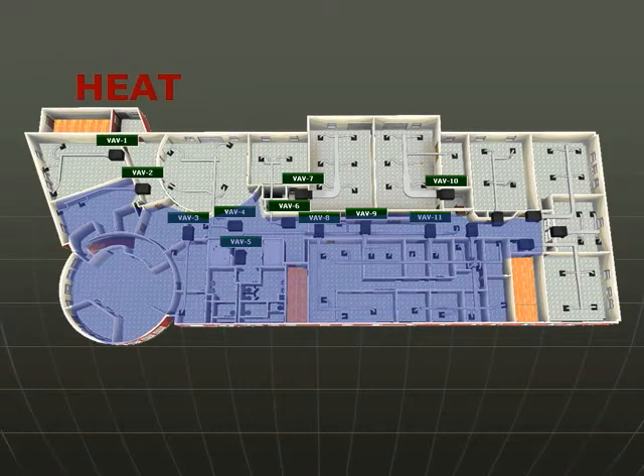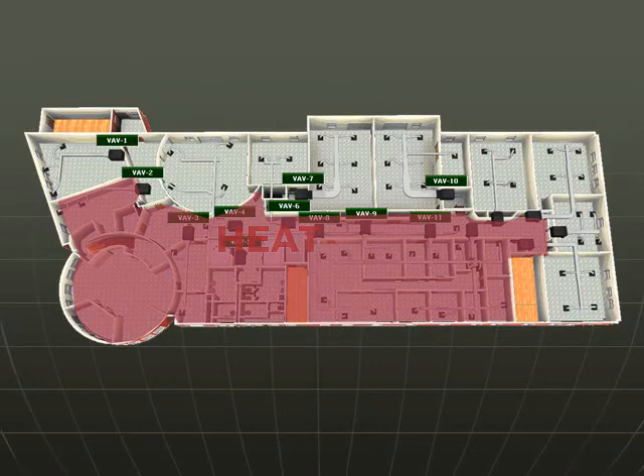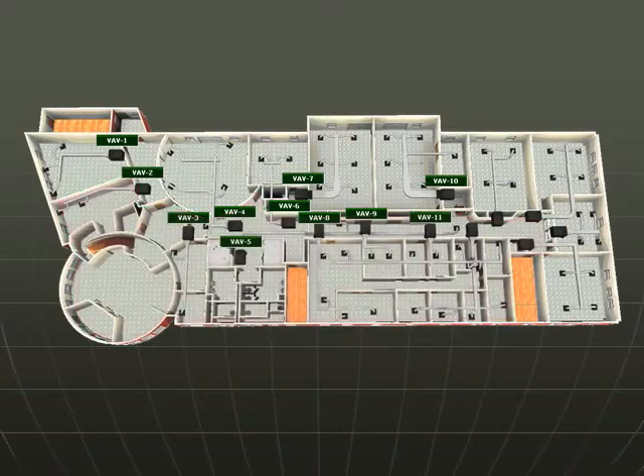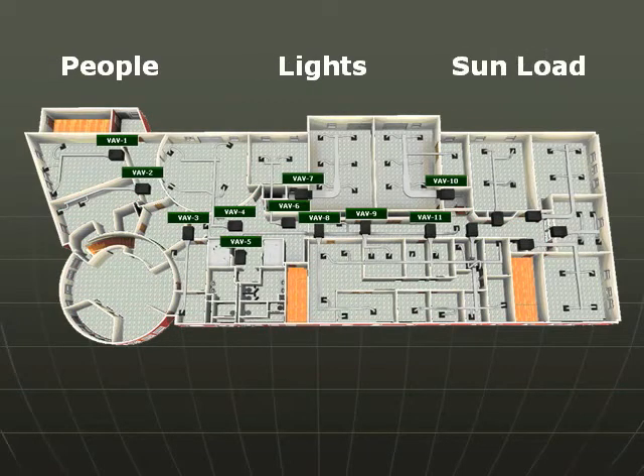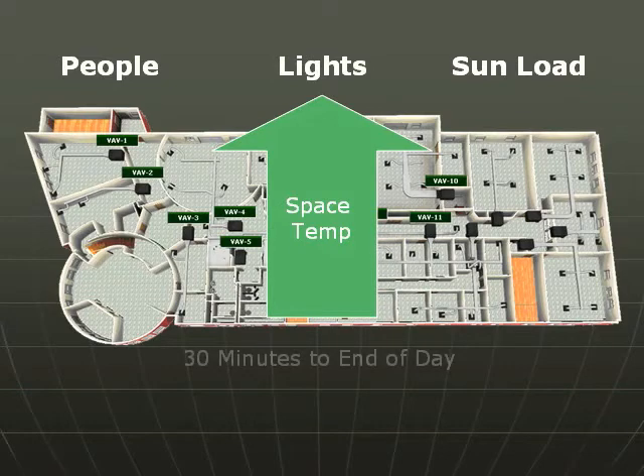Zone optimization allows you to concentrate your fan and heating energy to the coolest parts of your facility. It not only reduces warm-up time, but eliminates heating the sunny side of the building, then having to turn around and cool it down to remove the excess heat. The people, lights, and sun load are often enough to bring this space up to temperature. Optimized stop allows for the temperature to increase for the last half hour of the day.